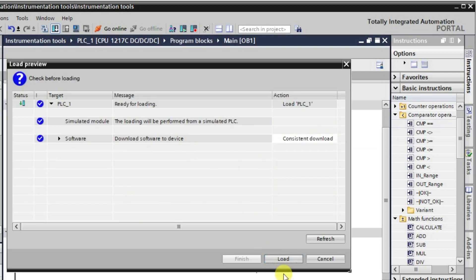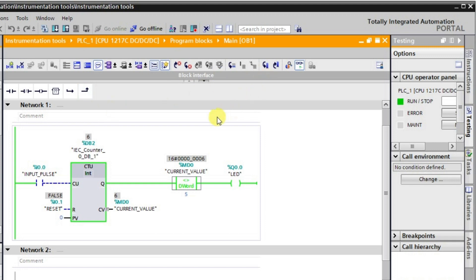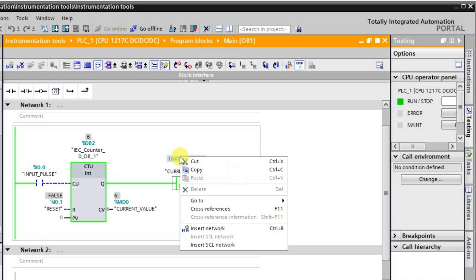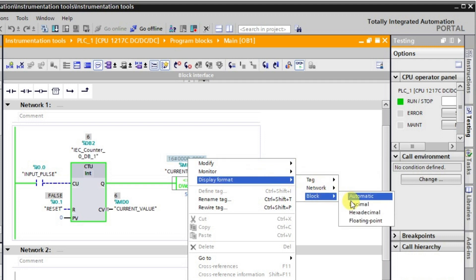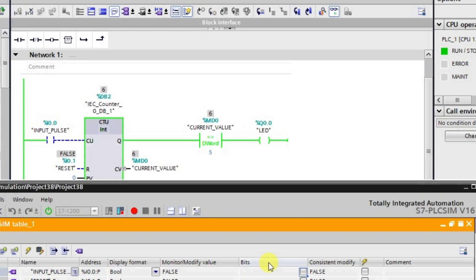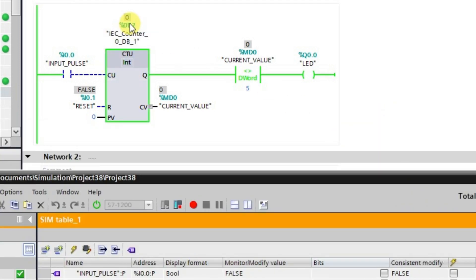After downloading the updated logic and going to monitor mode, we'll change the display format to decimal and reset everything. We can observe that when the current value is not equal to the comparator's preset value of 5, the output is in the high state. As we give pulses and the value approaches 5, the output remains high. When the value reaches 5 and both values match, the output switches to the low state.